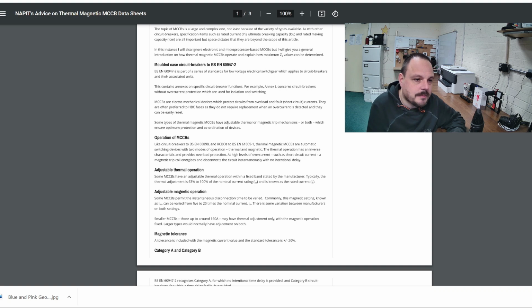Some types of thermal magnetic MCCBs have adjustable thermal or magnetic trip mechanisms, or both, which ensure optimum protection and coordination of devices. And that's where the application of these comes from. So as I said, if you have these in a main panel board, you will have sub-distribution boards as well. So when you're talking about selectivity, as you're stepping down through the sequence of your distribution circuits and your final circuits, being able to have some effect on the characteristics of the upfront protective device is really useful, certainly from a design point of view and from an installation point of view. And obviously those can change at times as well, so the fact that the adjustment is on there is quite helpful, I think.